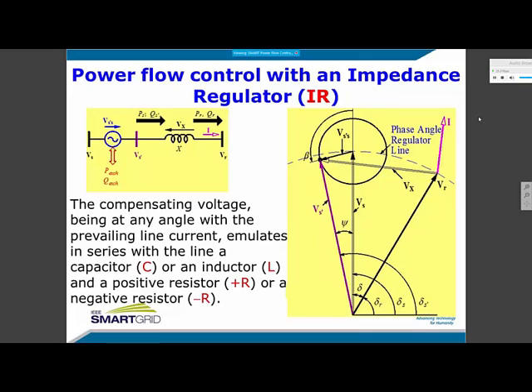The key to impedance regulation is to create a series-connected voltage, as is shown here, at any angle with the line current. Here is that voltage which modifies the original voltage to a new voltage, and the difference is the compensating voltage. The in-phase component of this compensating voltage with respect to the line current emulates positive R. The out-of-phase component of this voltage emulates negative R. The quadrature component leading the line current emulates an inductor, and the quadrature component lagging the line current emulates a capacitor. But the actual series voltage is a composite voltage that is at any phase angle with the line current.